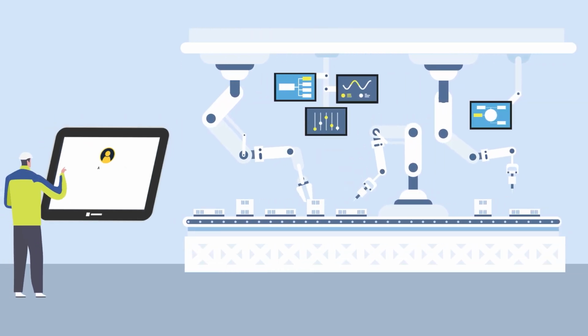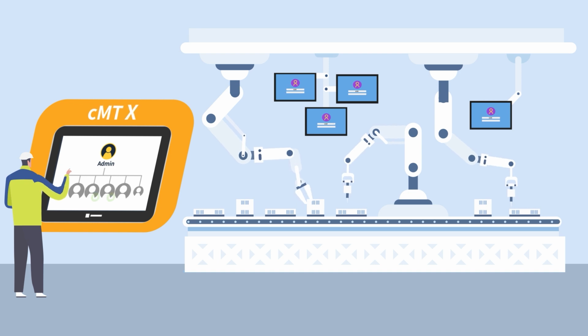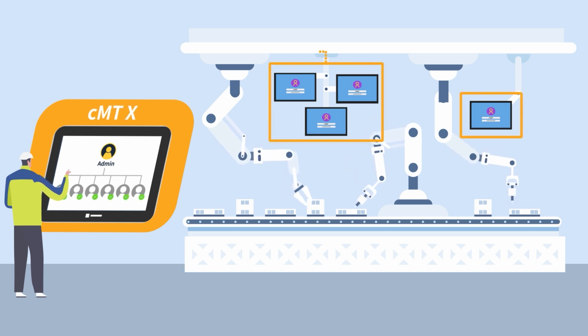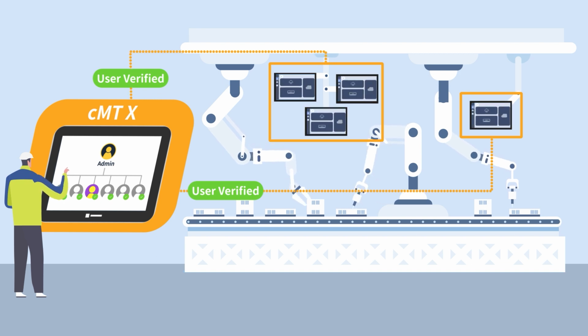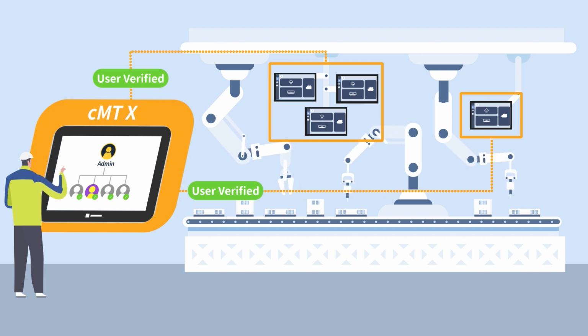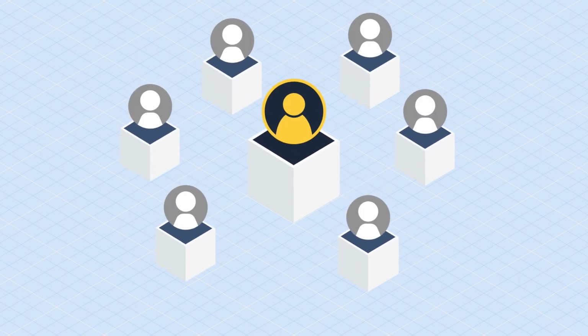On the other hand, if using an HMI as a central server, the HMI that is processing login now just has to connect to the central HMI instead. Similar to LDAP, when any change to a user account is necessary, such change only needs to be updated in this central HMI. With centralized UAC management, HMI management is a lot easier and more efficient than it used to be.